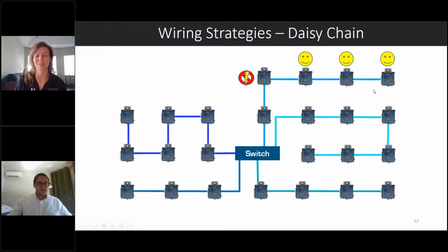And a quick tip would just be to make sure that the switch supports PoE. That's my last plug for that slide. Do your homework and make sure the switch supports PoE. Yep, absolutely. So this slide is showing us a few separate daisy chain links coming from a central switch. But one thing I want to point out is that you should be on the lookout for controllers that have the ability to continue communication onto the next controller if there is a loss of power event. So if this controller was to lose power, you can still have communication continue on to these other smiley face controllers I have over here. That's definitely a nice added functionality to have. It's really just a relay that snaps that communication together so it can continue on.